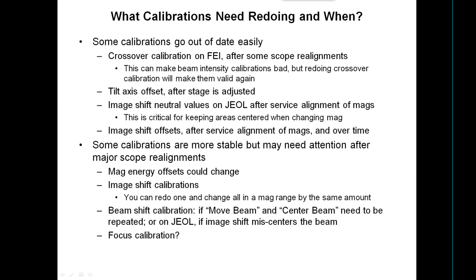A common question is what calibrations need to be done and when. Some calibrations go out of date very easily. The crossover calibration on the FEI goes out after some scope realignments, and this can make beam intensities bad — especially if you fall into the wrong side of crossover. But all you have to do is redo the crossover calibrations; it shifts everything and keeps track of what they are, making the calibrations valid again.